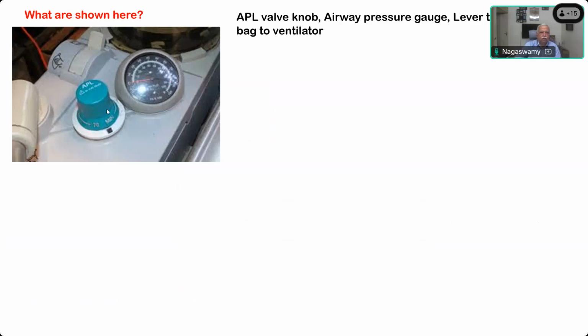Airway pressure gauge. Then the toggle between the bag and the ventilator. Yeah, it's called the machine lever, to switch from bag to ventilator. So APL valve knob, airway pressure gauge, lever to change from bag to ventilator. These are the 3 components which are shown here.